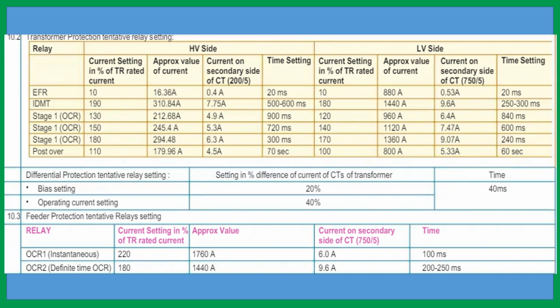But I have shown you our system. What is the system? For any fault, the maximum fault current, we have shown it is near about how much? 6400 for the 21.6 MVA transformer, and we are setting the instantaneous overcurrent relay 25% more than it. So here, what is the 25%? 1.25 times 6400. You can find out how much it is coming. You have to convert it, because when we reflect it to the 132 kV side, it will reduce. Then times 1.25, how much is it coming? Next day I will tell you.